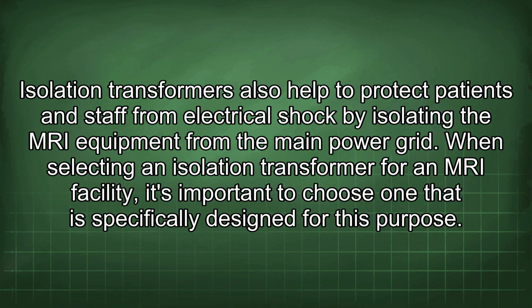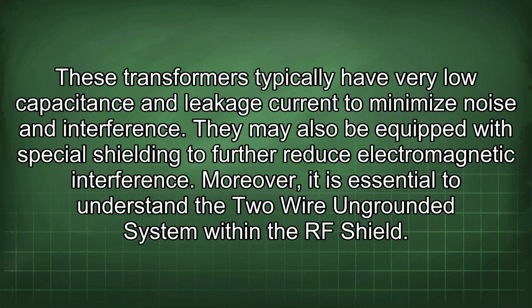When selecting an isolation transformer for an MRI facility, it's important to choose one that is specifically designed for this purpose. These transformers typically have very low capacitance and leakage current to minimize noise and interference. They may also be equipped with special shielding to further reduce electromagnetic interference.